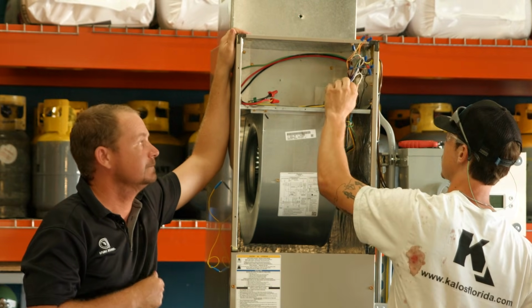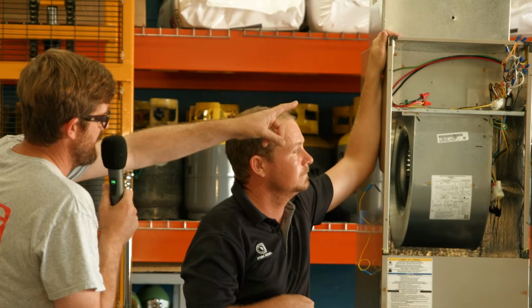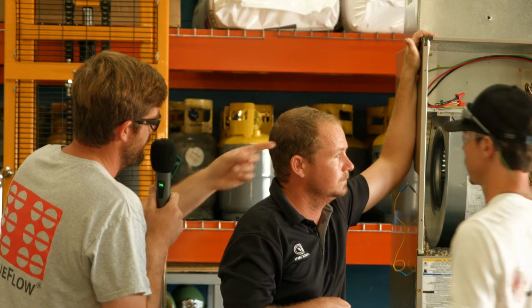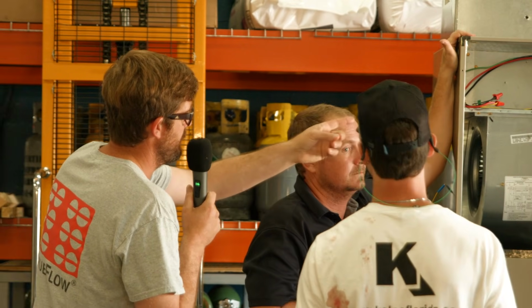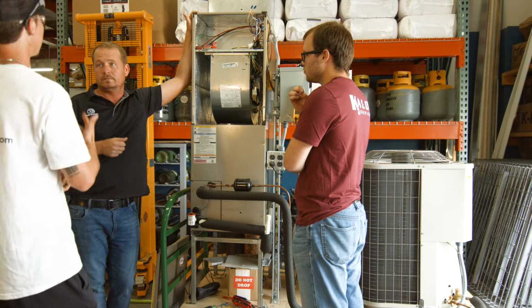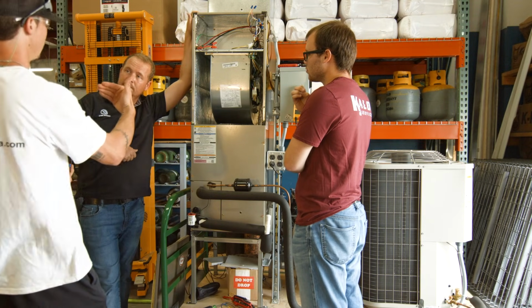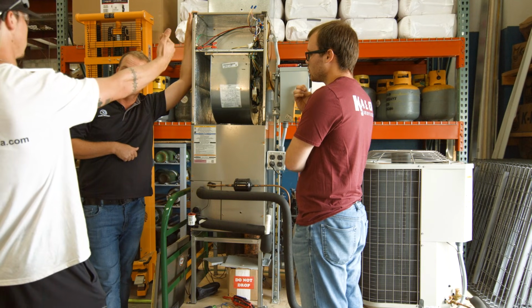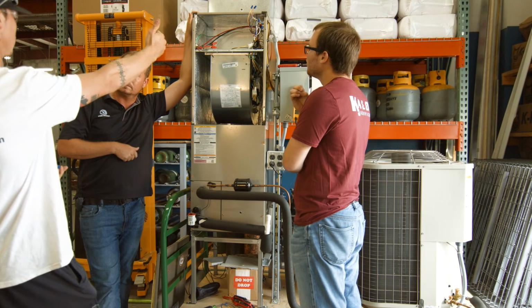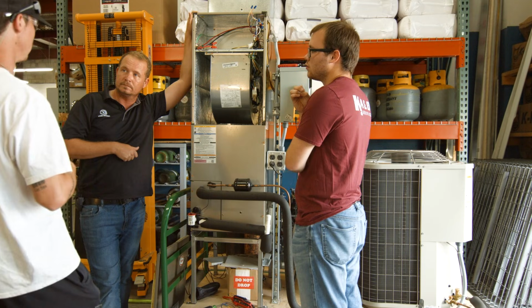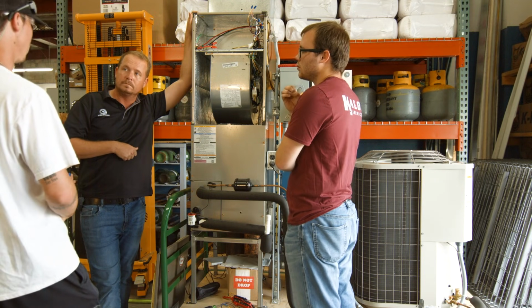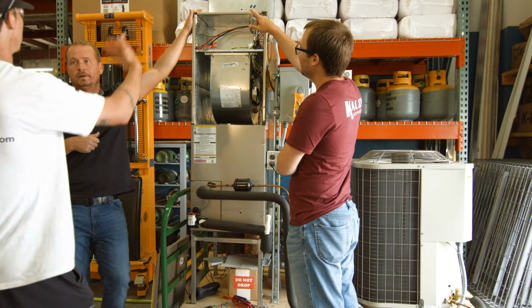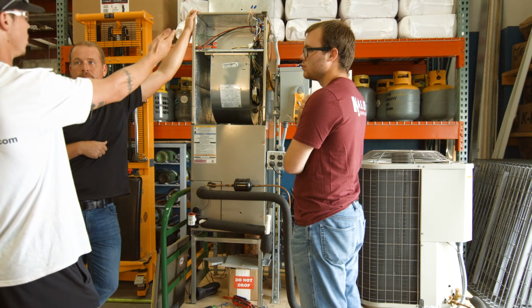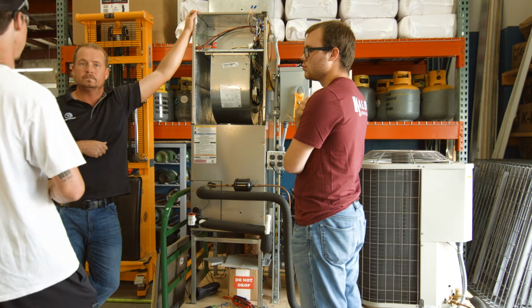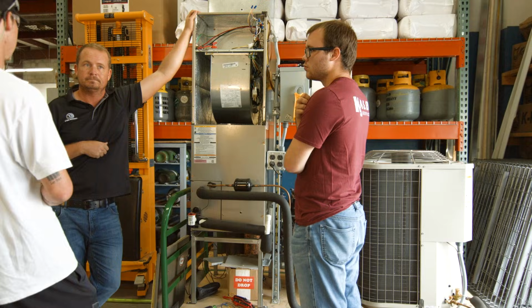I would also be doing a good visual inspection on any of the field wiring connections and even the factory ones to make sure something's not rubbed or crossed. Or a brand new install, either way, it doesn't matter. If it's a service call, as soon as I take off the panel, I'm looking at the wires that are wire nutted all together, and I'm trying to confirm what wires they have going where. Potential damage that I'm concerned about. No exposed copper, and also the correct size wire nuts, and that they're actually connected correctly together.